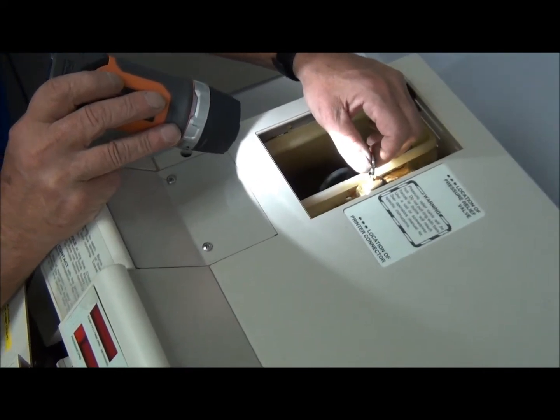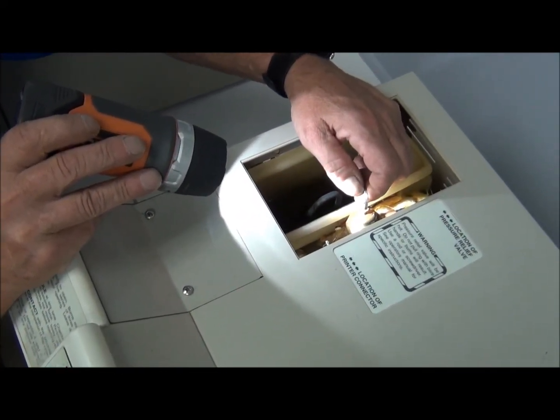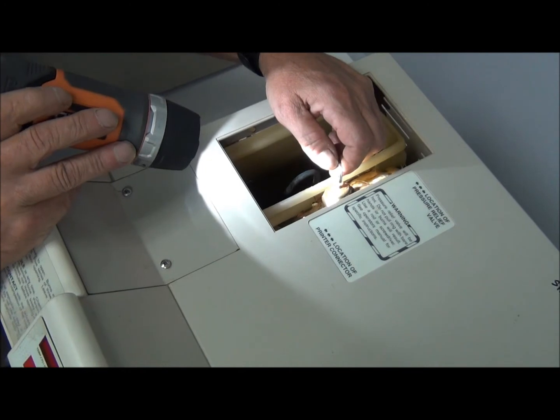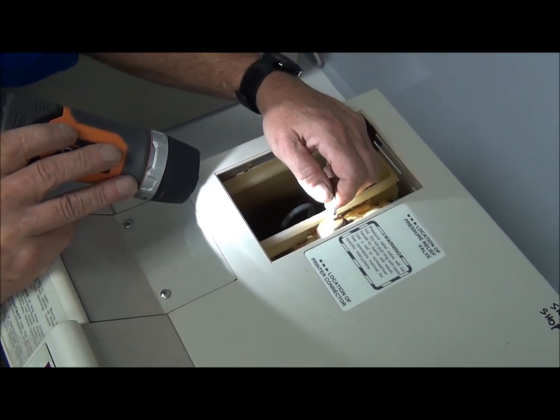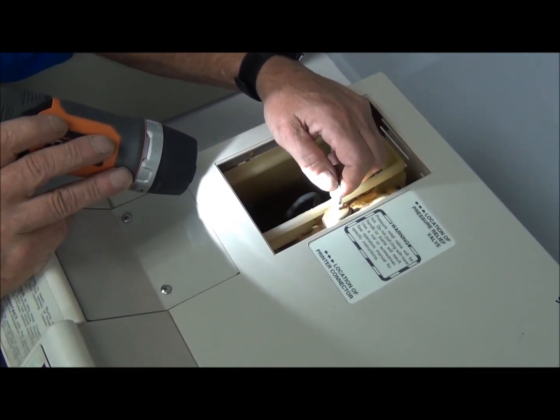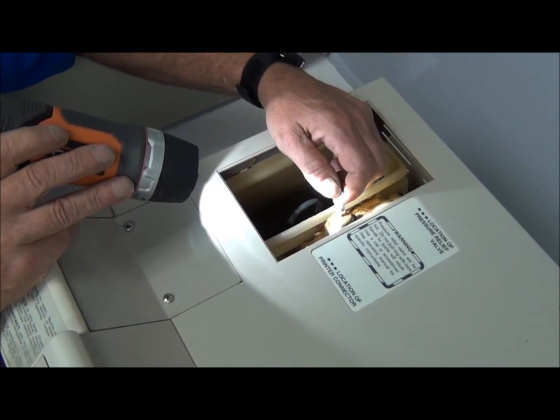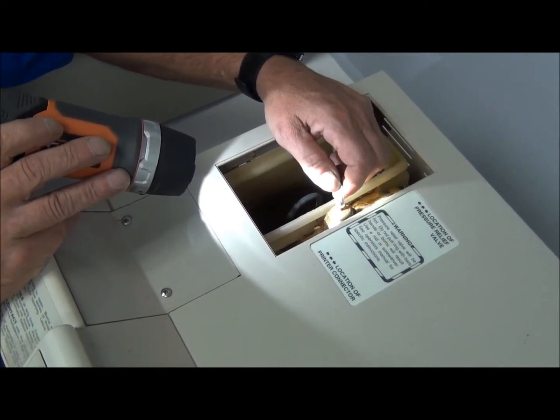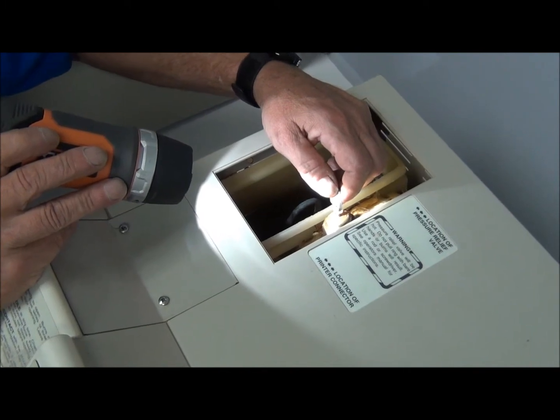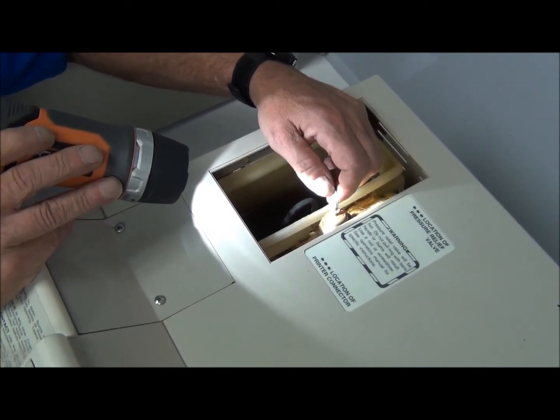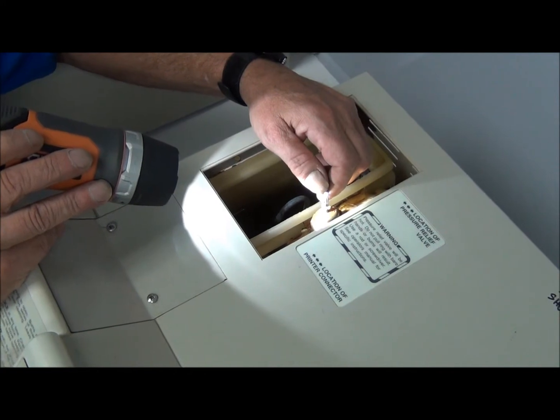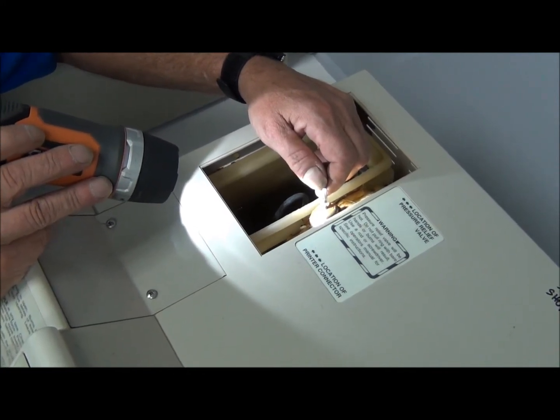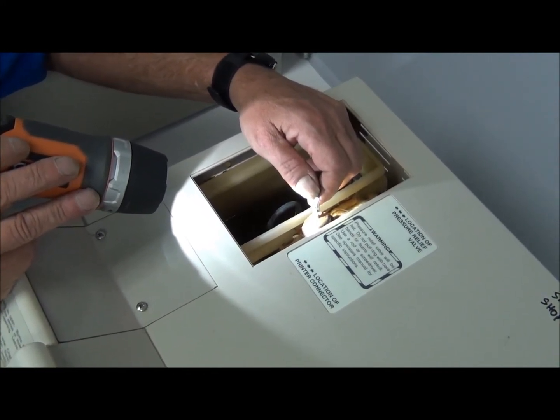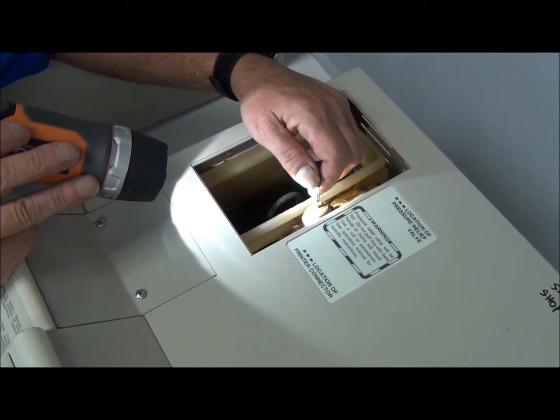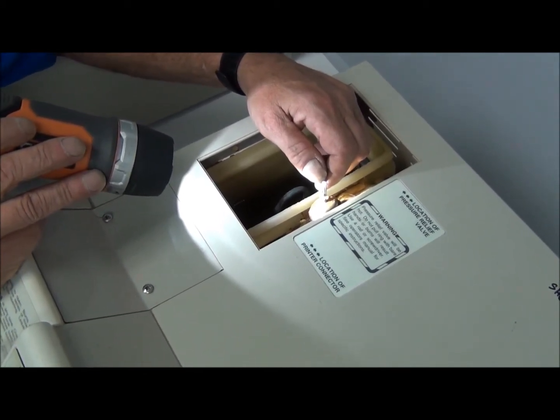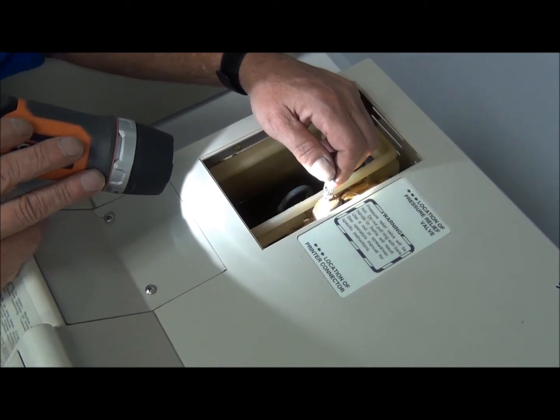Ladies and gentlemen, the PM calls to release the safety valve during pressure. Do not release the safety valve during pressure unless you have a replacement safety valve in stock and you're sure of it. Usually when you interrupt the integrity of the safety valve, it rarely seats back and it calls for a replacement. Then again, another revenue generator. Have it in stock. A sterilizer is an emergency item. Please try to stock at least the safety valves and door gaskets for them, guys, okay?